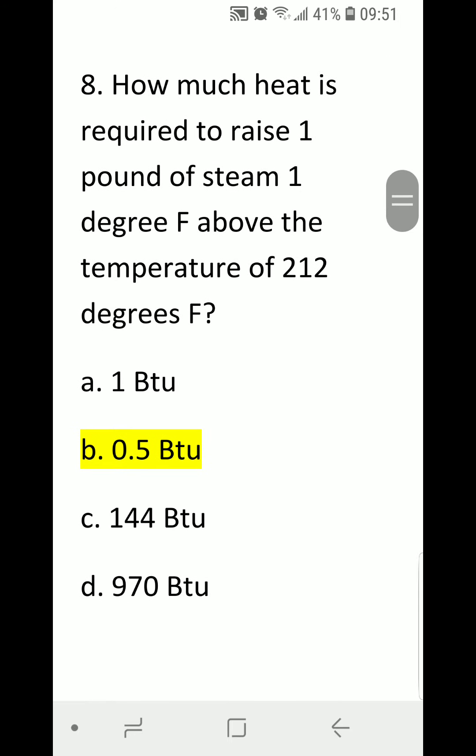Number eight: How much heat is required to raise 1 pound of steam 1 degree Fahrenheit above the temperature of 212 degrees Fahrenheit, which is the boiling point of water? A) 1 BTU, B) 0.5 BTU, C) 144 BTU, or D) 970 BTU. The correct answer is B, 0.5 BTU.